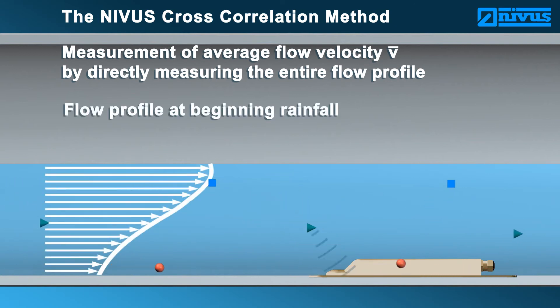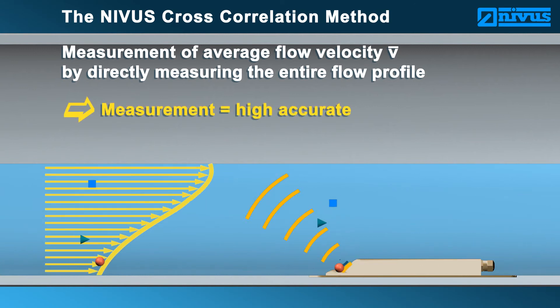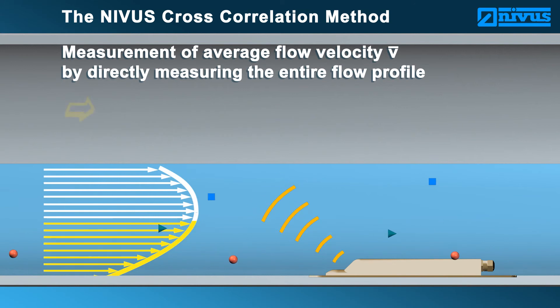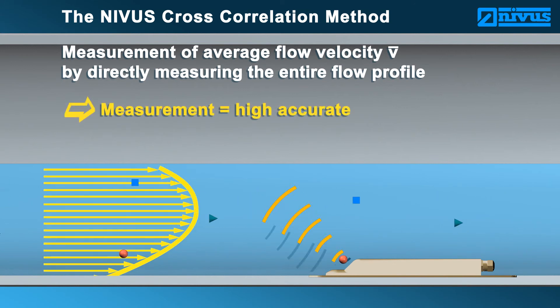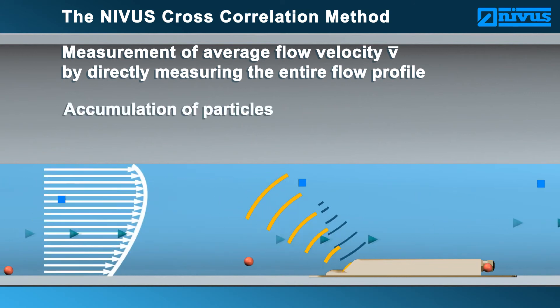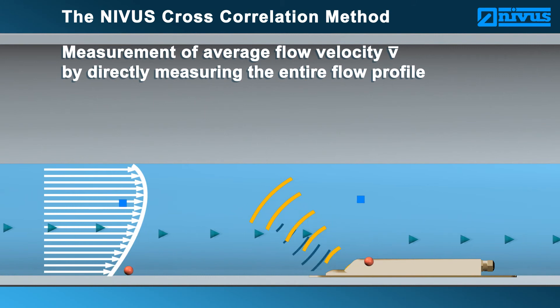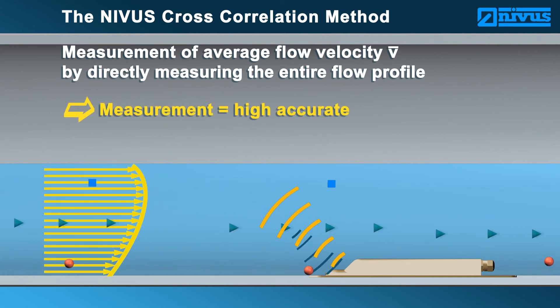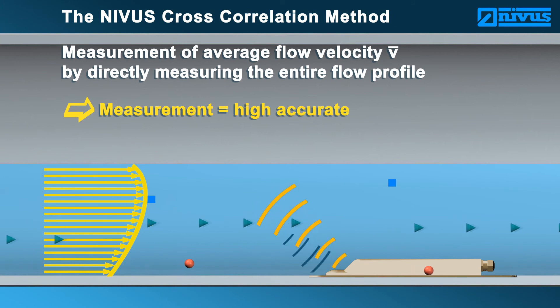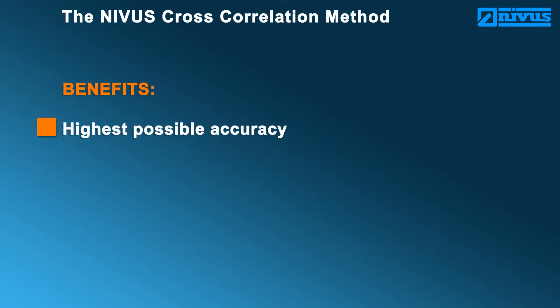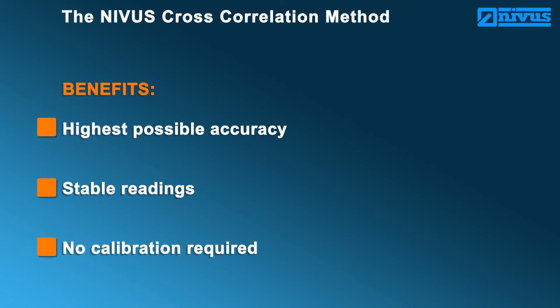The sensor even detects flow profile changes due to events such as rainfall, and the measurement remains highly accurate. The measurement results remain highly accurate even in case of backwater formation caused by obstacles such as sedimentation, elbows or throttle equipment. Even accumulation of particles within the medium has no effect on the measurement. The NIVUS cross-correlation method offers: highest possible accuracy, stable readings, and no calibration required.